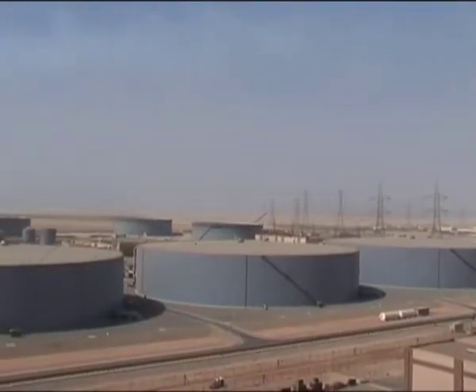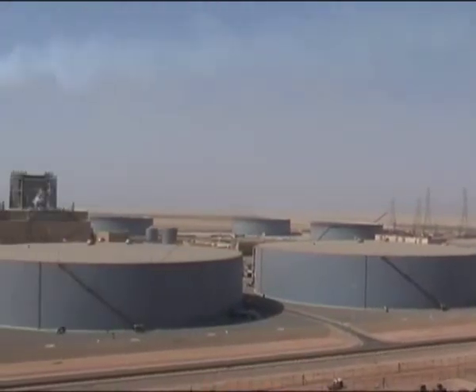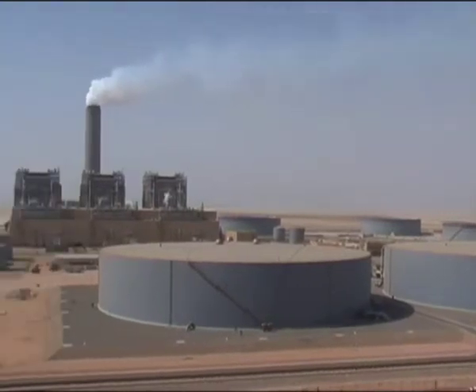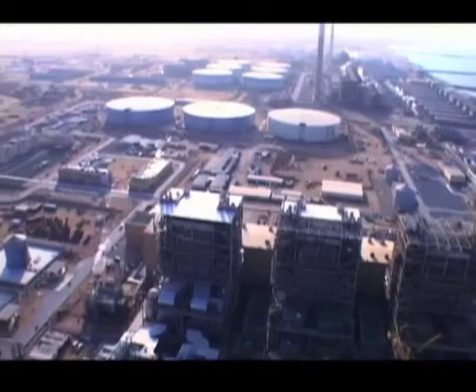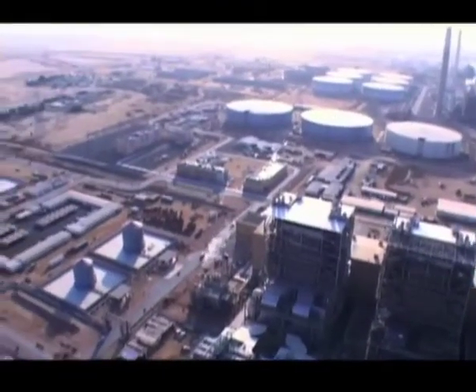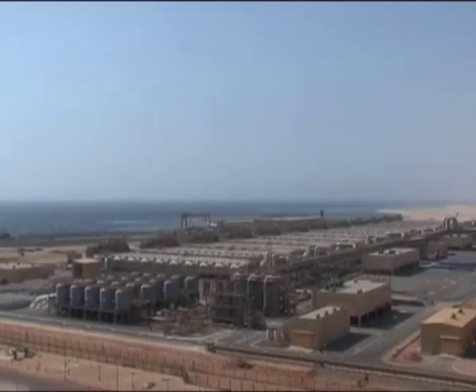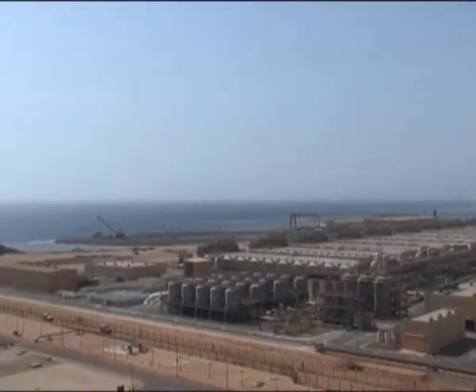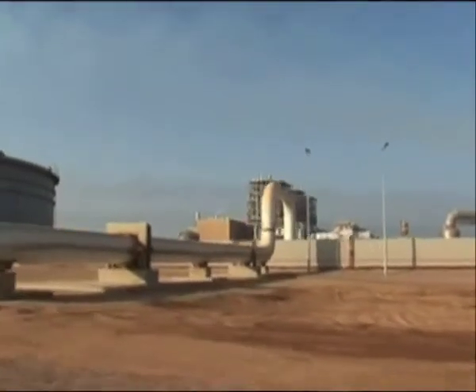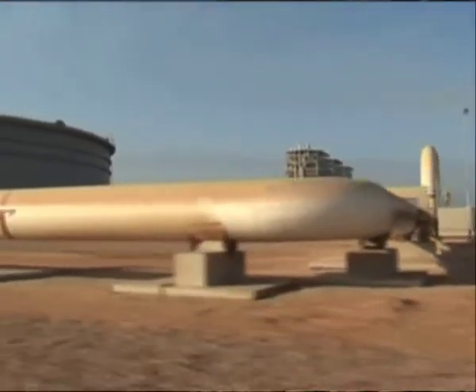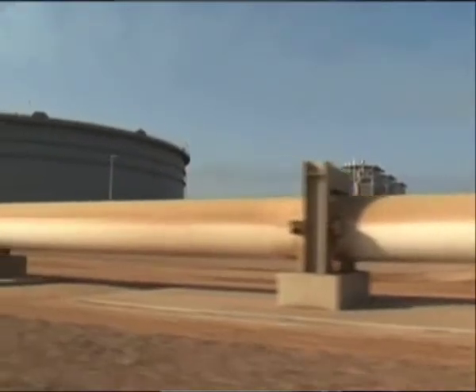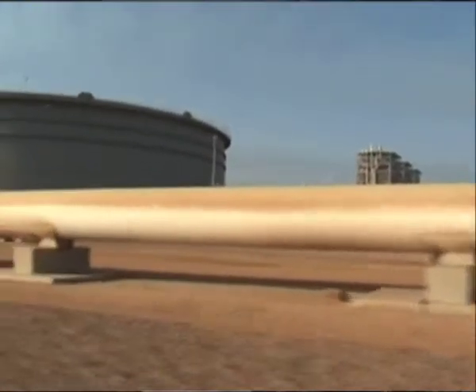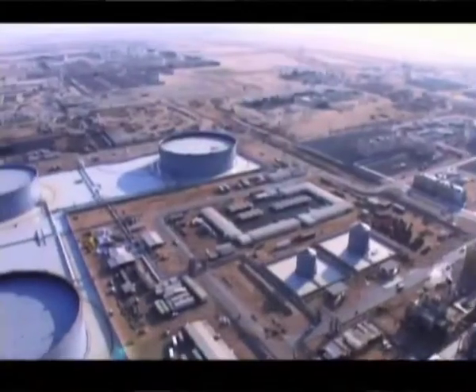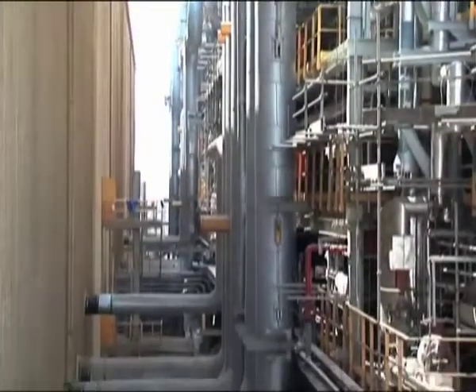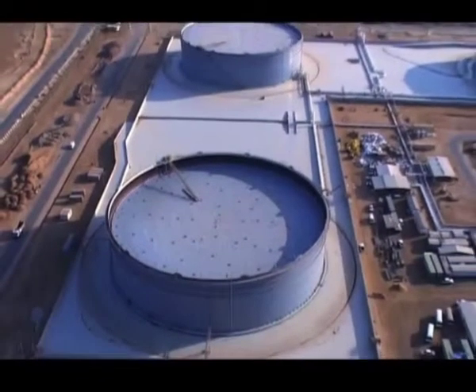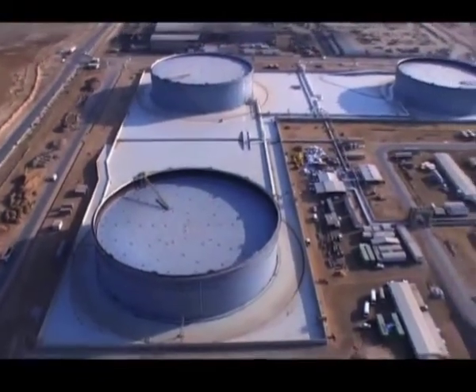Shuaiba IWPP is configured into three groups, each group comprising an oil-fired boiler and steam turbine for power generation, each rated at 400 megawatts, and four units of multi-stage flash evaporators for the production of potable water. The boilers are fired by crude oil, which is shipped by tanker to an existing jetty adjacent to the project site. A special fuel facility transfers the oil through 5 kilometers of pipeline to on-site storage tanks. The total capacity of the tanks is 330,000 cubic meters, sufficient for 30 days nominal plant operation.